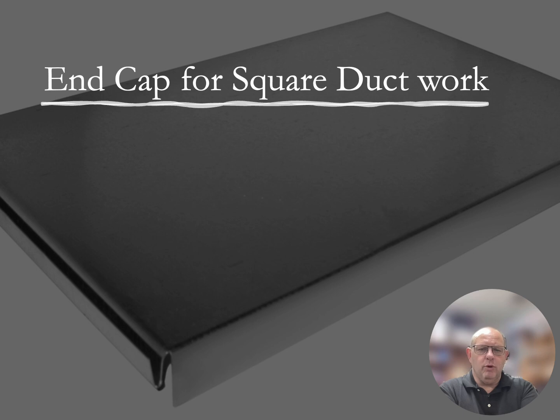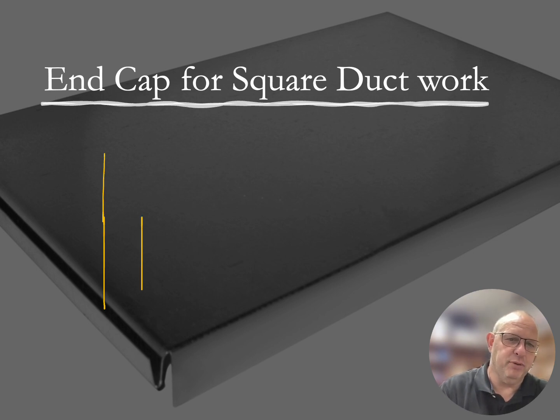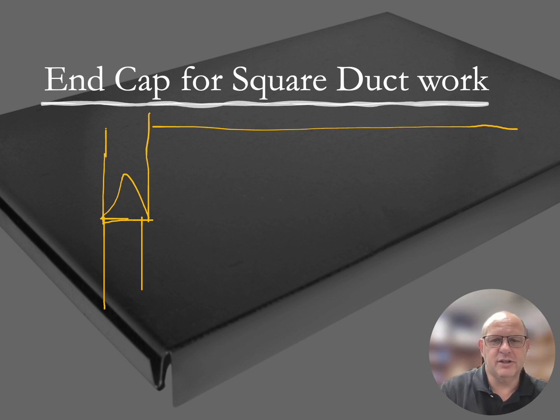So as we're coming along, we're running that ductwork or that main trunk right down the center of the house. Hopefully, you've got your furnace. Off of that, you've got your plenum, maybe your A coil sitting on top of your furnace right in here. We've got our plenum coming up, and then we're going to run our trunk this direction. At the end of our trunk, we're going to put an end cap, and that's what we're seeing in the picture right here. It's an end cap that's going to stop that airflow from going any further.